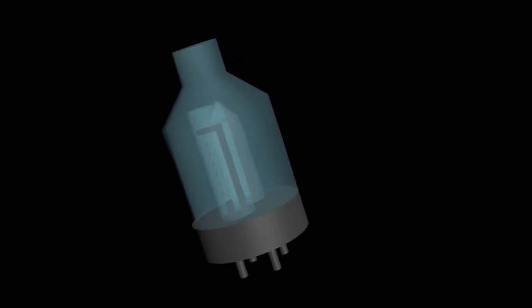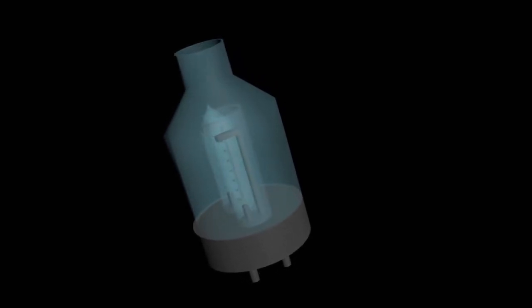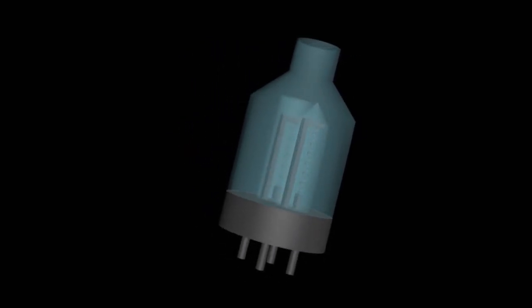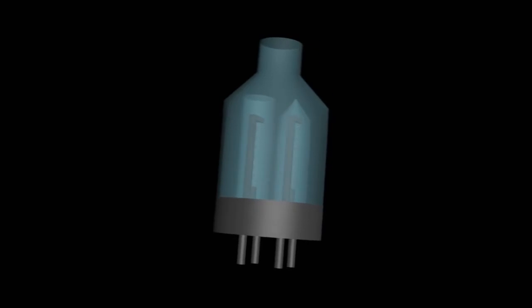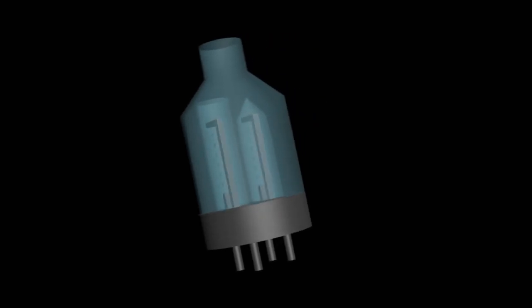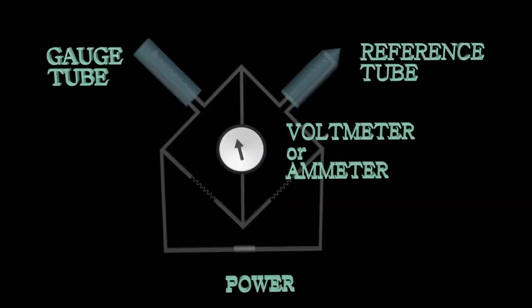The system consists of two tungsten filaments, a power source and a voltmeter or ammeter. One of the filaments is placed in the gauge tube and is exposed to the environment where the pressure is measured. The other filament, however, is placed in a sealed reference tube filled with gas at constant pressure.